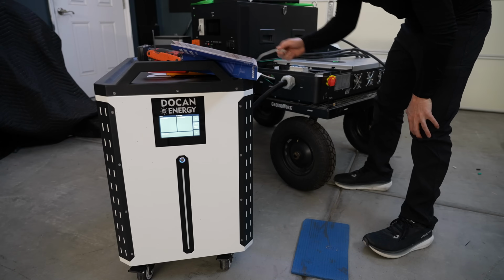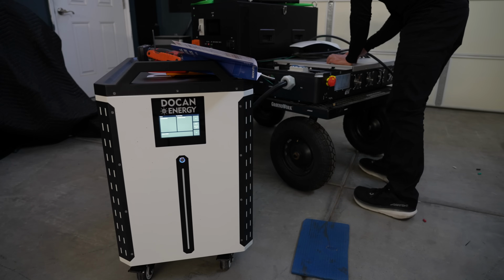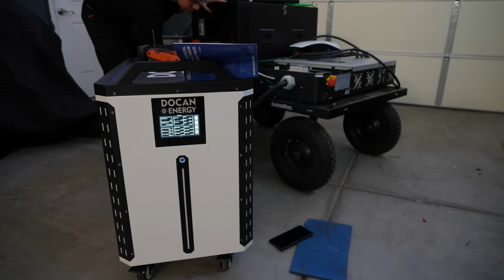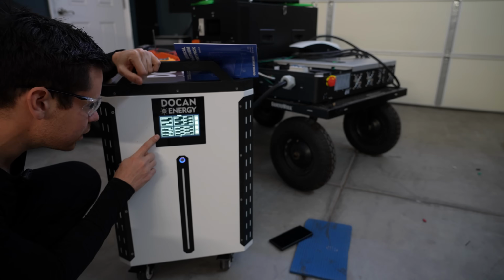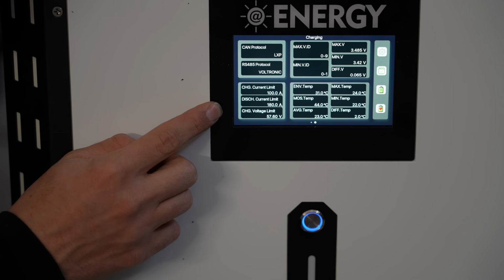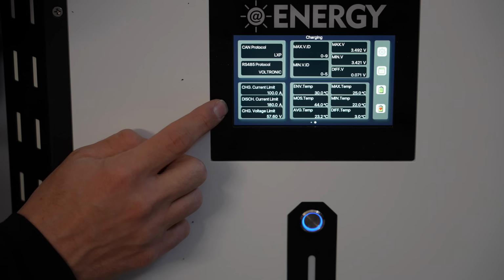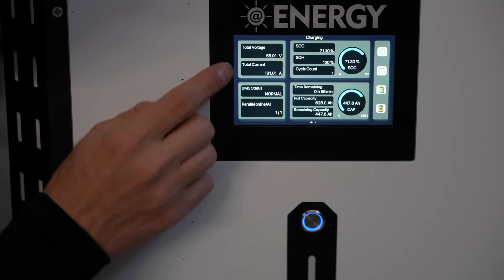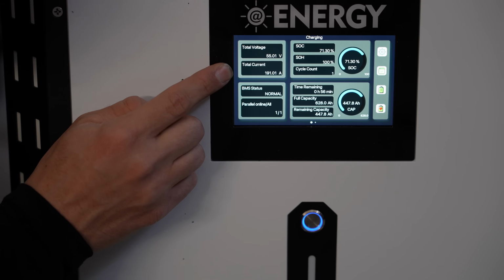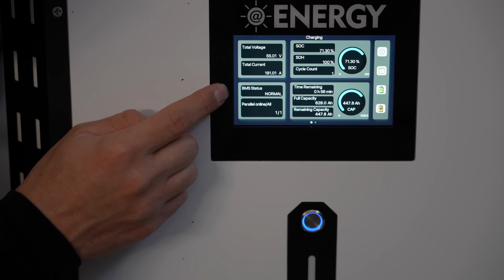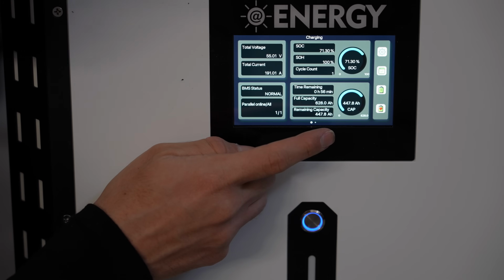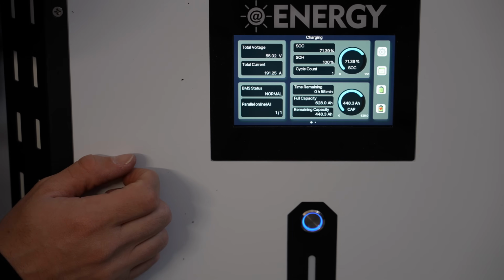So we're going to disconnect this cable, set it to lead acid battery. Now it should work, and we're charging with 191 amps. That's weird — the charge and discharge current limit that magically appeared when I set up communication is back, but check this out, we are exceeding it and it's not doing anything, and we don't have any alarm codes. That is very strange, but it's working, so let's continue the test.